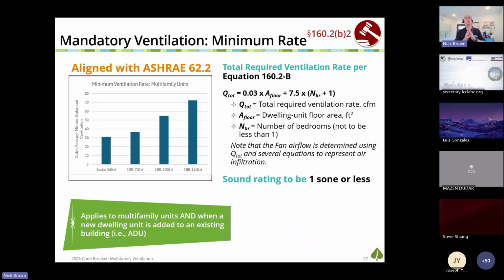So how is the minimum airflow rate calculated for dwelling units? Well, it uses this ASHRAE 62.2 formula, the same one that's used for single family. So the airflow is a function of the conditioned floor area and the number of bedrooms. The CF1R form that your energy consultant produces will show that minimum airflow rate. And just a quick note, it differs in different climate zones slightly because of different wind ratios, wind speeds. And so the airflow of the fan is added to the airflow from infiltration that's assumed according to that wind rate and the height of the building and a complicated formula. So just suffice it to say, the windier the climate zone, the less the airflow required for your fan.